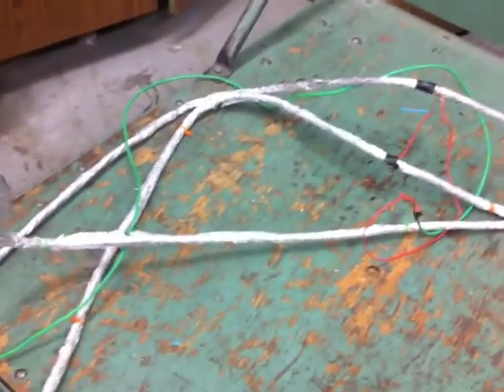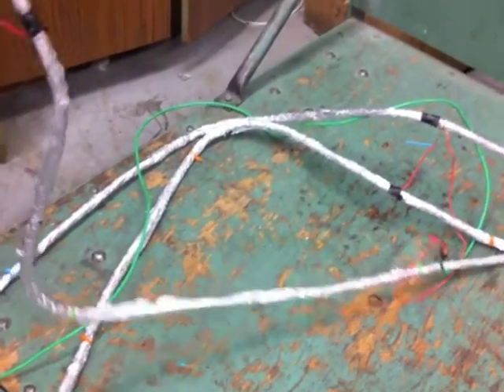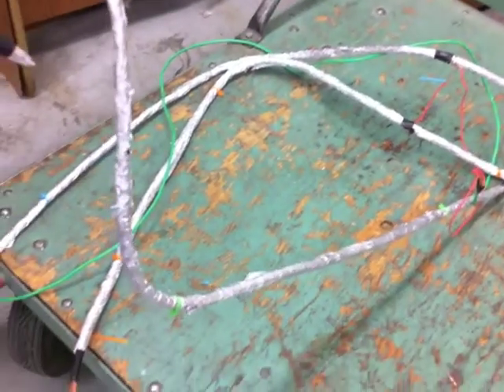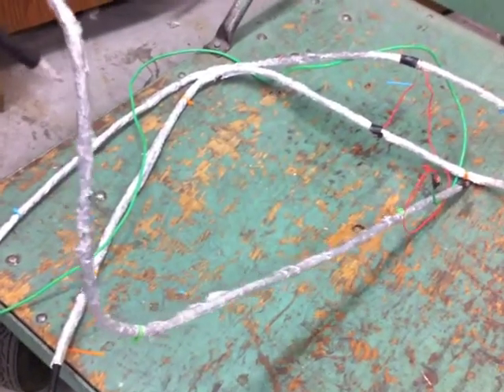The welding cable connecting the motor with the motor controller can potentially become a broadcasting antenna of RF noise. This noise can interfere with analog and digital vehicle data, such as the motor resolver and temperature information. To combat this, the cable is shielded with aluminum foil, and the cable shield is grounded to the motor chassis.